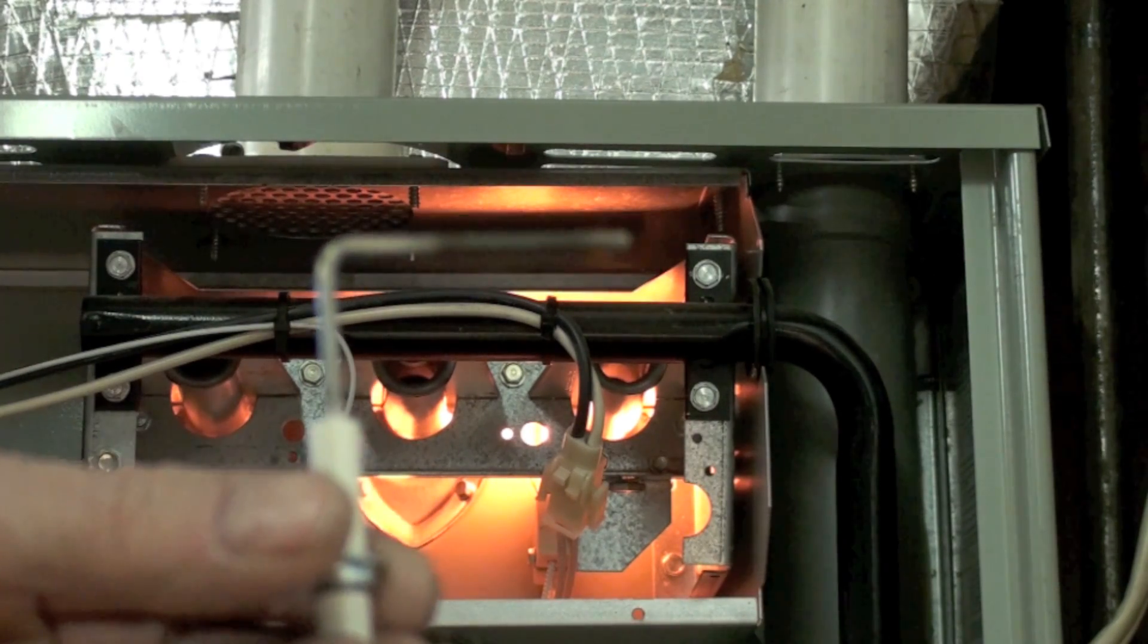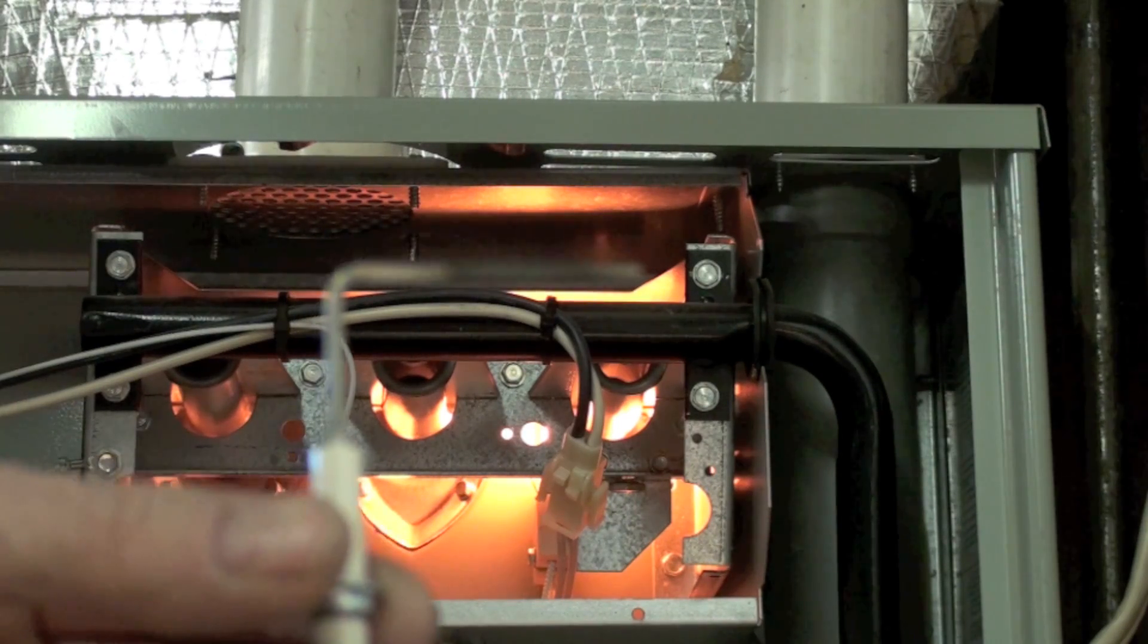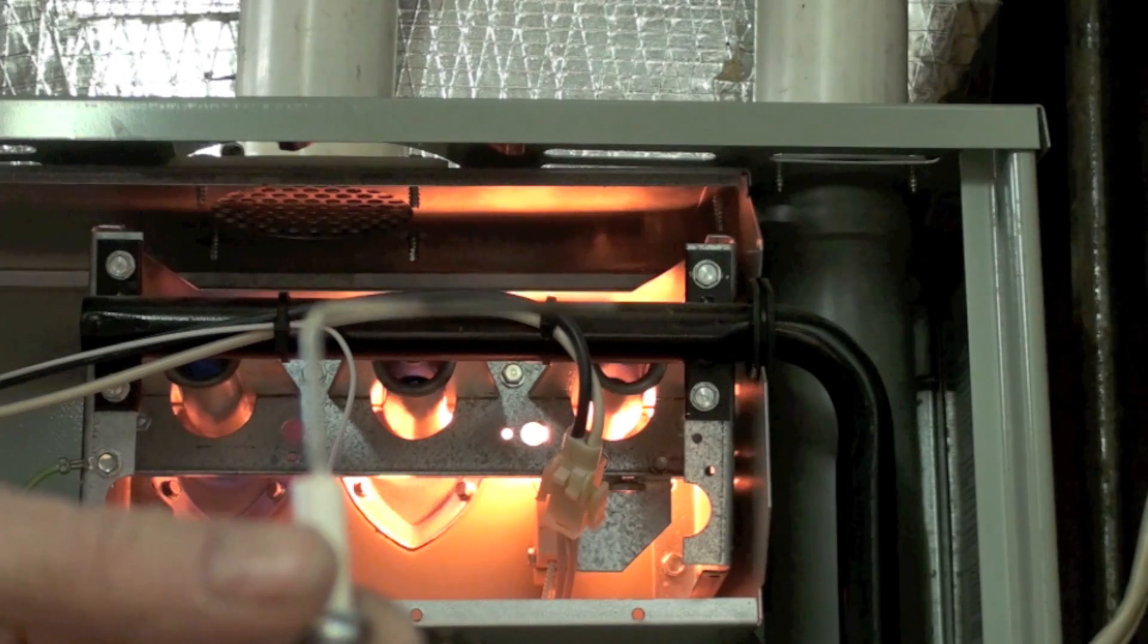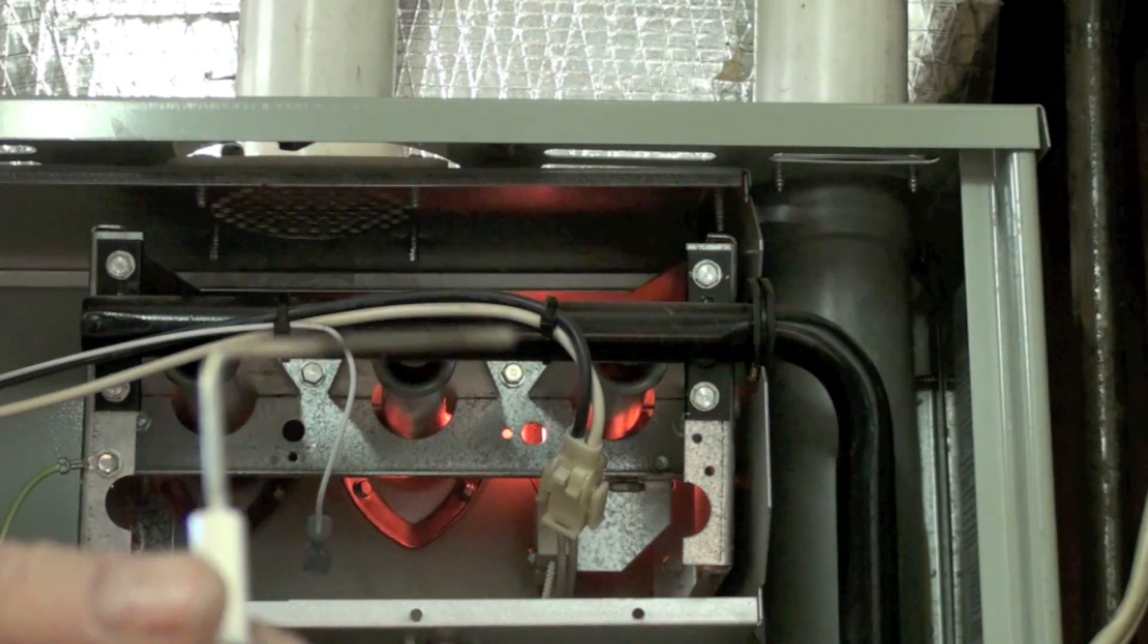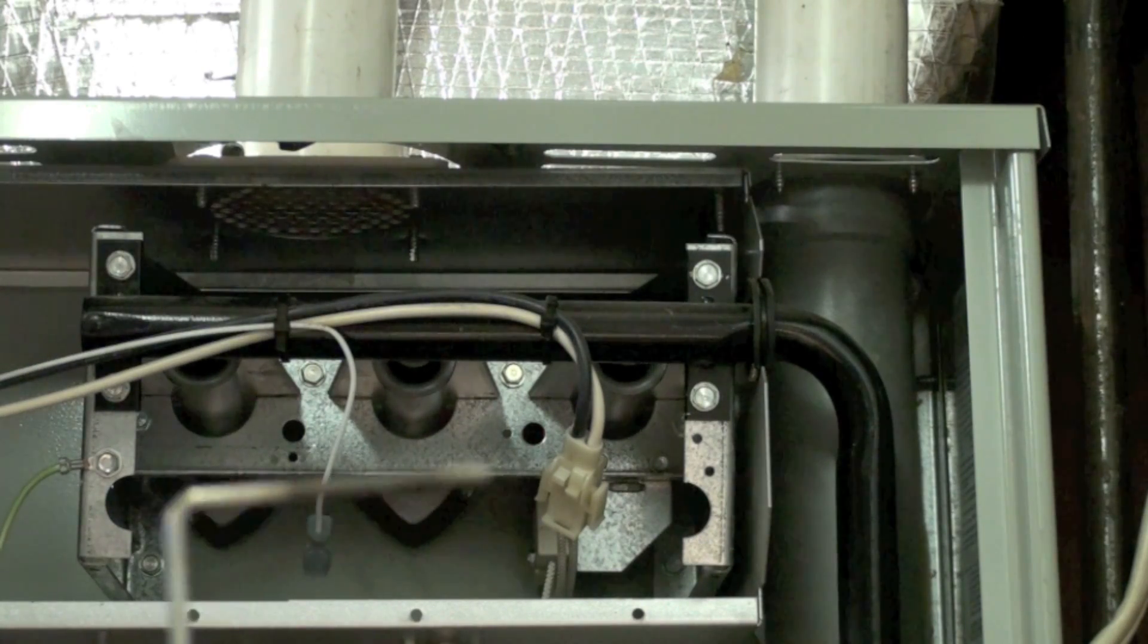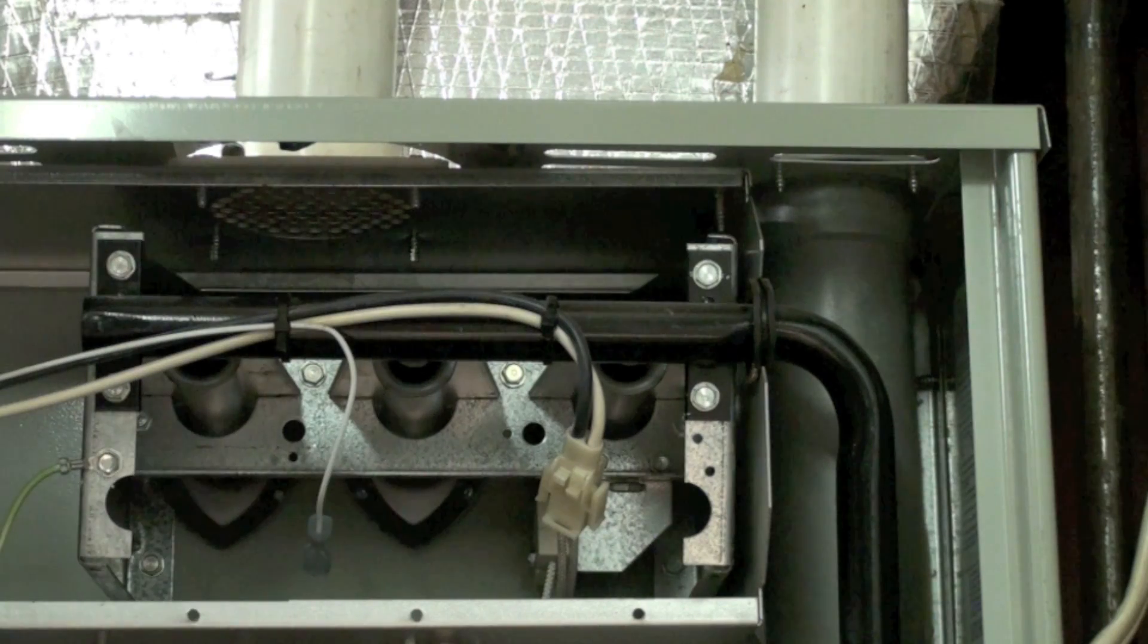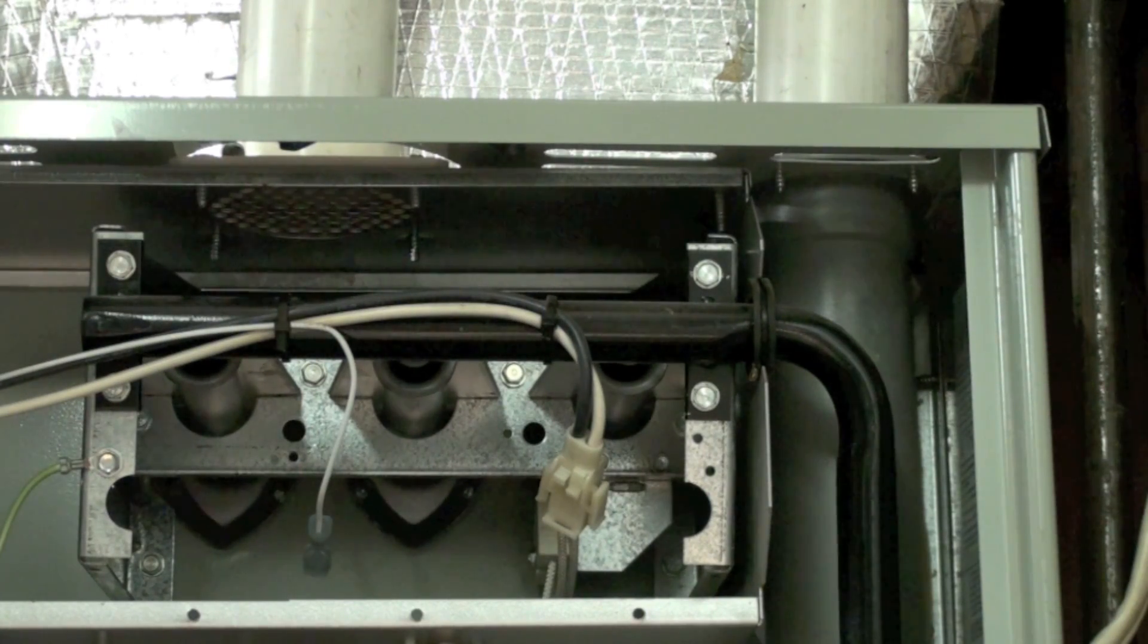It's trying one more time, not going to start because the flame rod's not in there. This can be cleaned with steel wool, sandpaper, whatever you want to use. I would not be too aggressive on this thing because the stainless steel does actually have a kind of chrome coating on it. Don't be too aggressive but don't be too afraid of it.